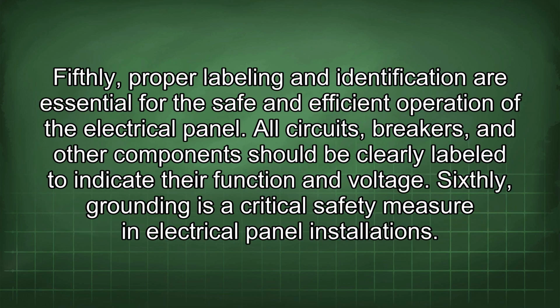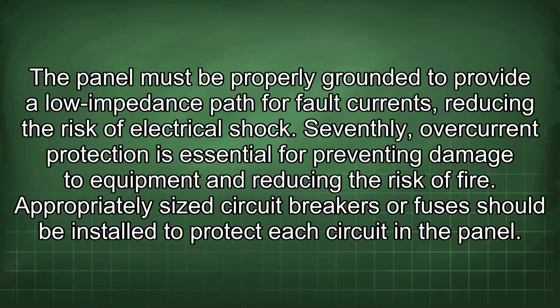Fifthly, proper labeling and identification are essential for the safe and efficient operation of the electrical panel. All circuits, breakers, and other components should be clearly labeled to indicate their function and voltage. Sixthly, grounding is a critical safety measure in electrical panel installations. The panel must be properly grounded to provide a low impedance path for fault currents, reducing the risk of electrical shock. Seventhly, overcurrent protection is essential for preventing damage to equipment and reducing the risk of fire.